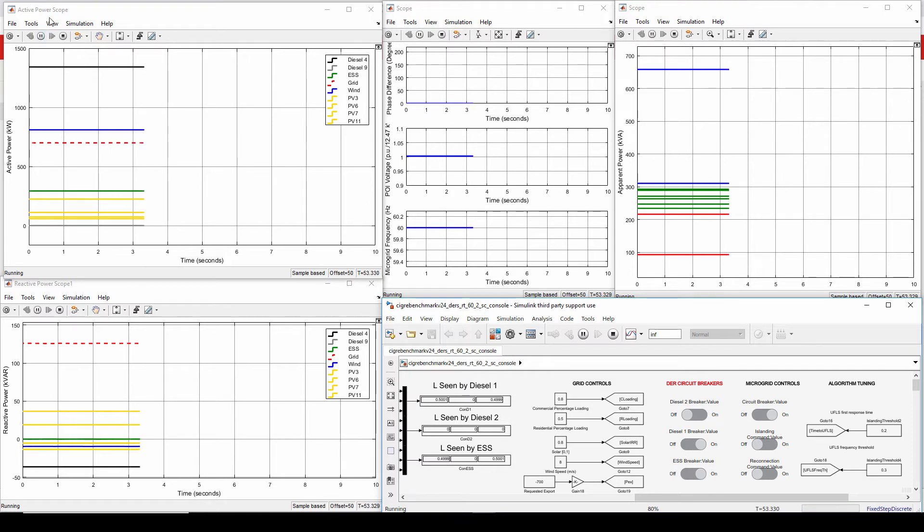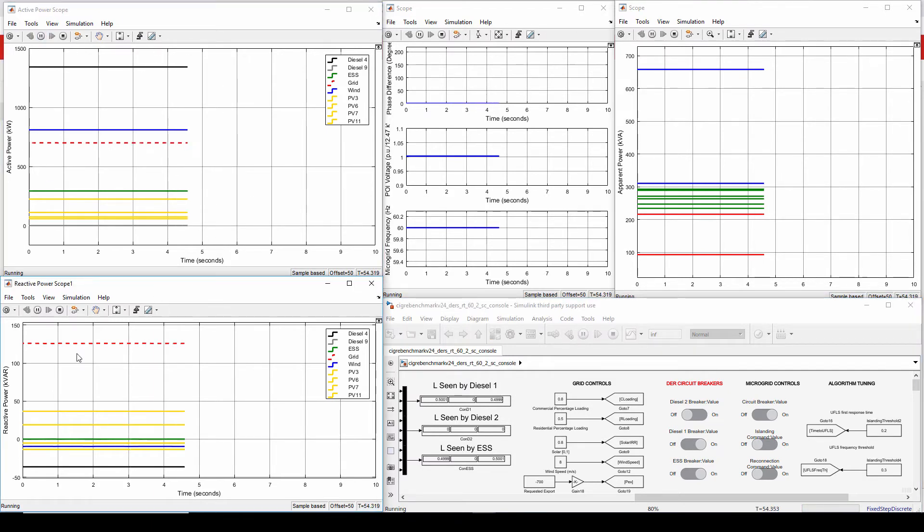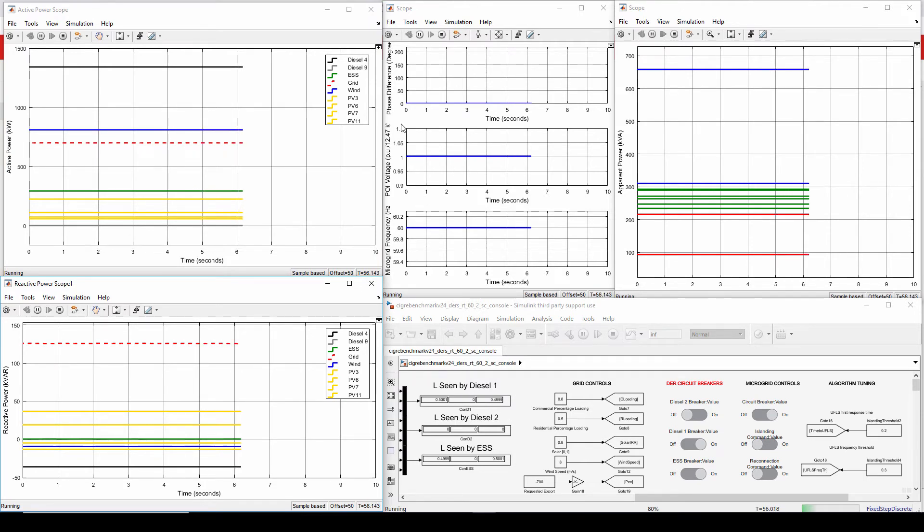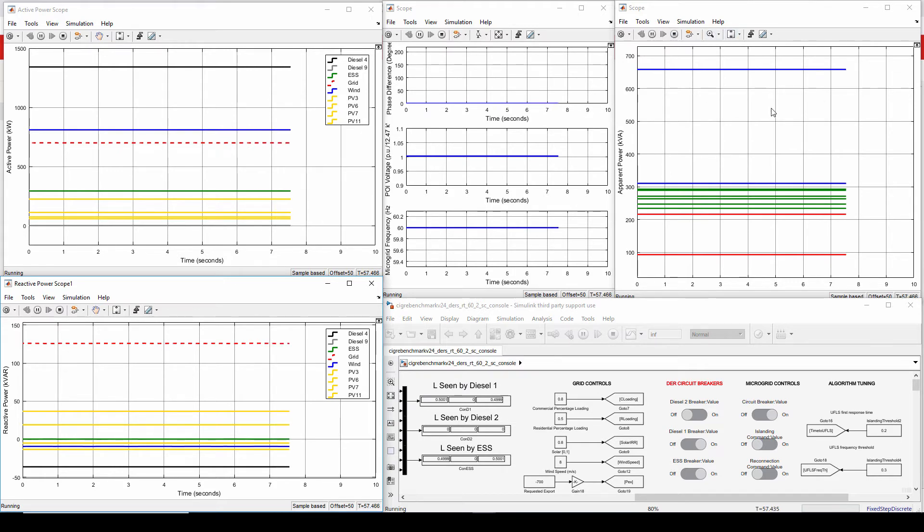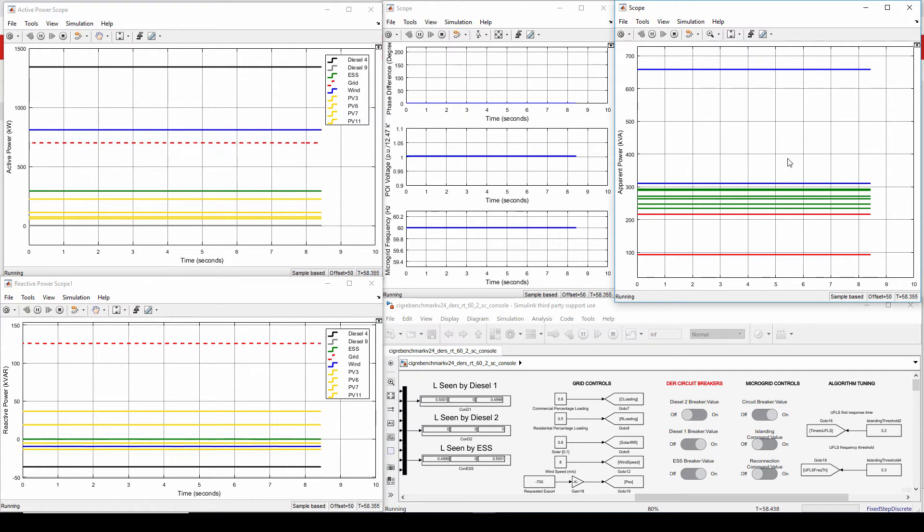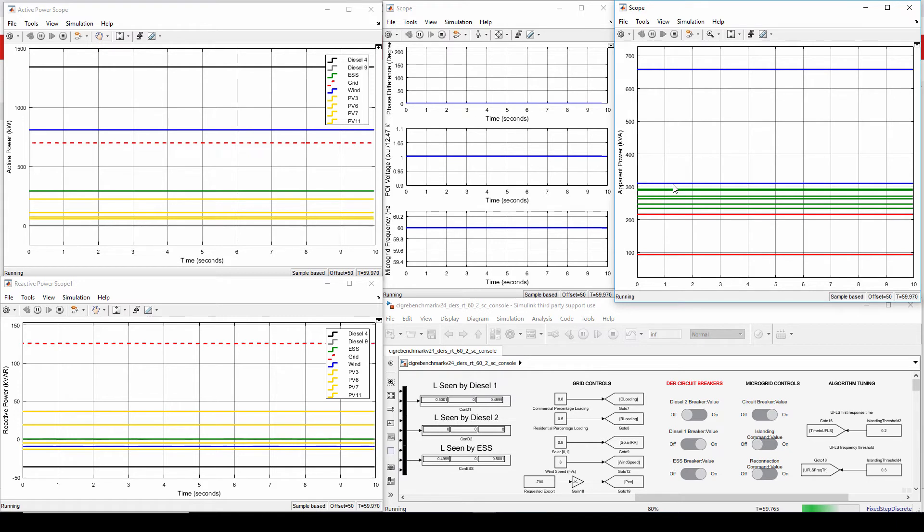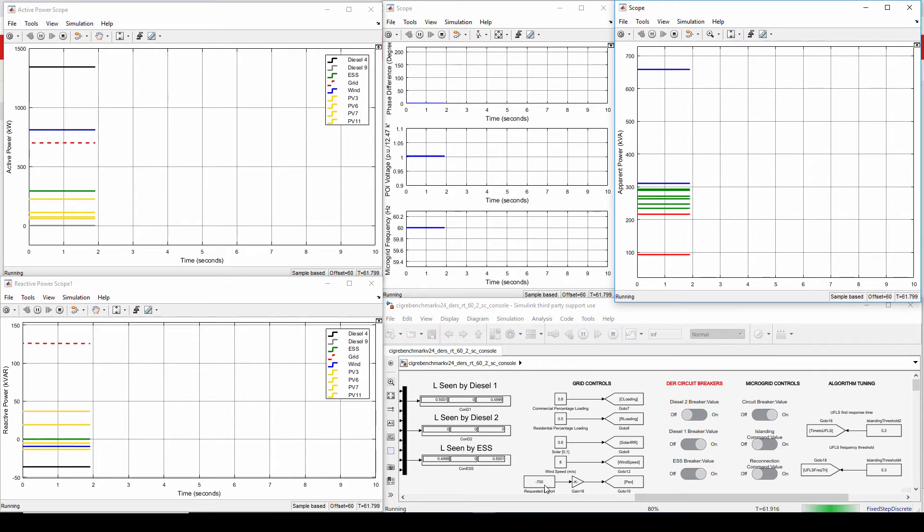So here we have the active power scopes in kilowatts. Here the reactive power scopes. Here we have the microgrid frequency, POI voltage, and the phase difference. And here we have the active power scopes of every load in the system, the blues being the non-critical loads. Okay, so first of all, I would like you to observe that the requested power is at 700 kilowatts, and that's what it's being regulated at.